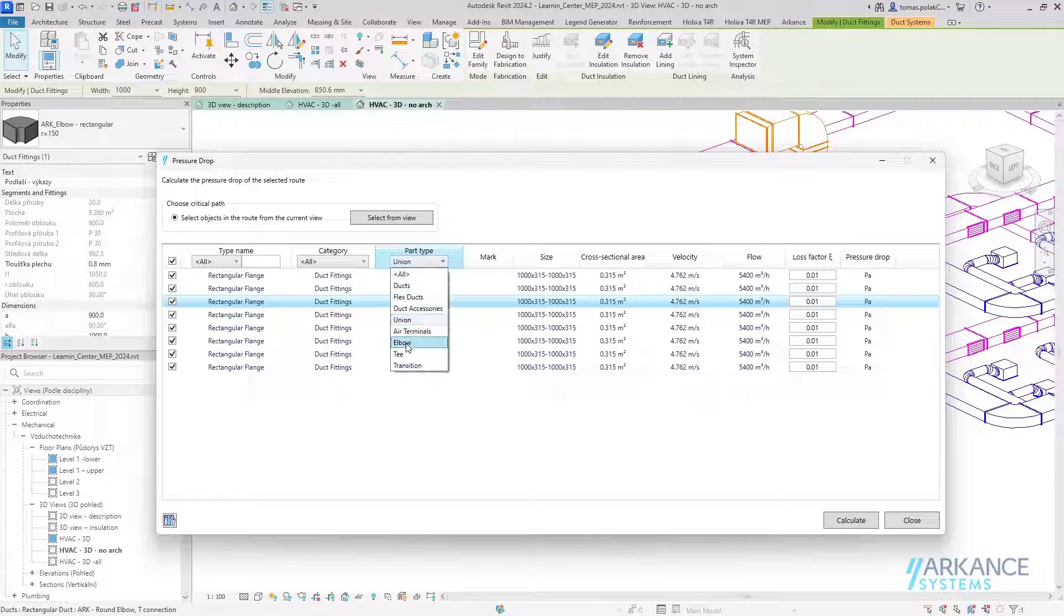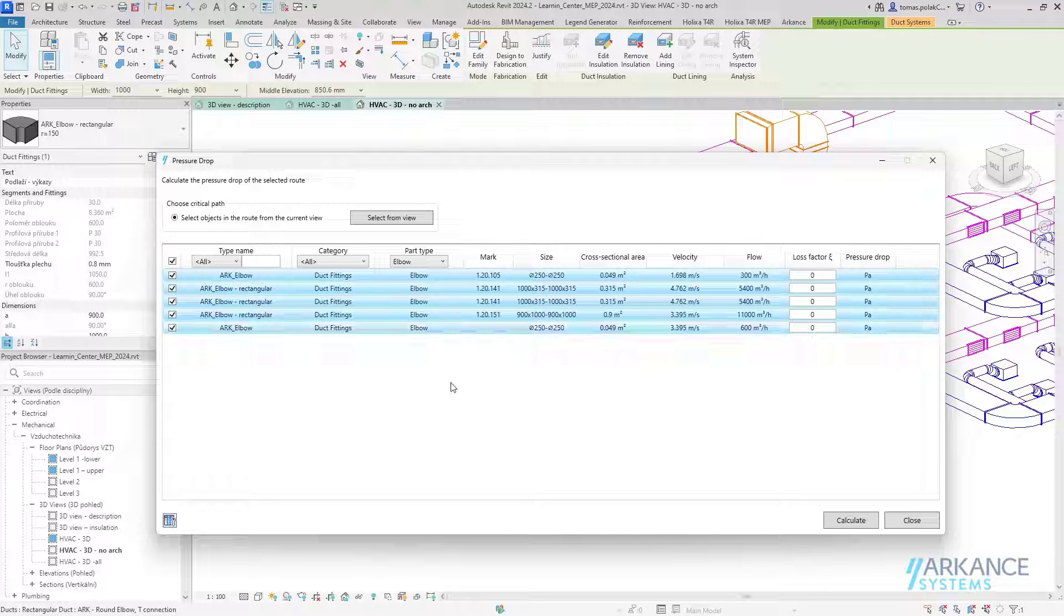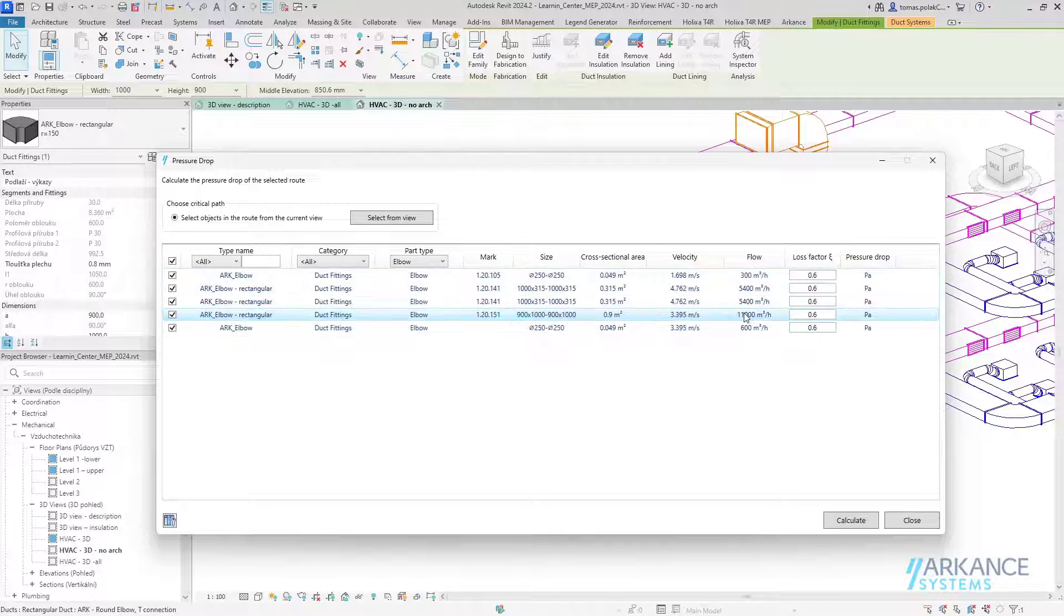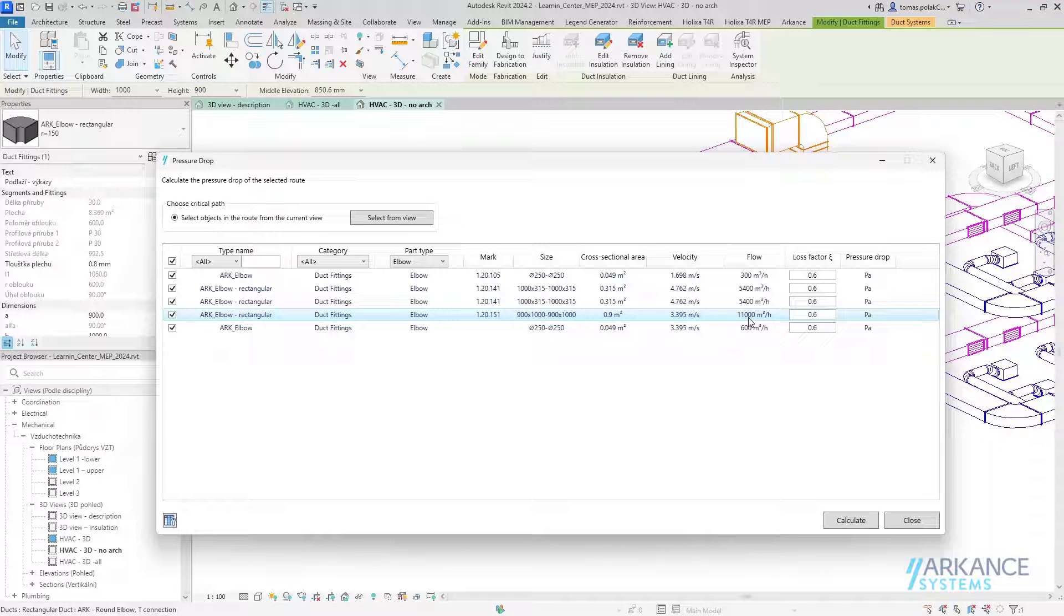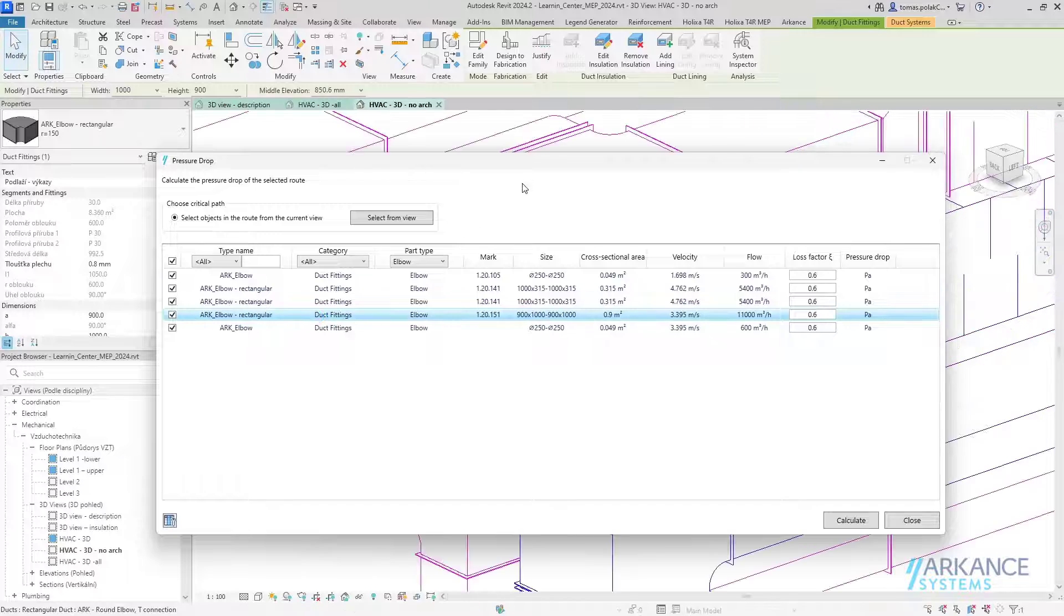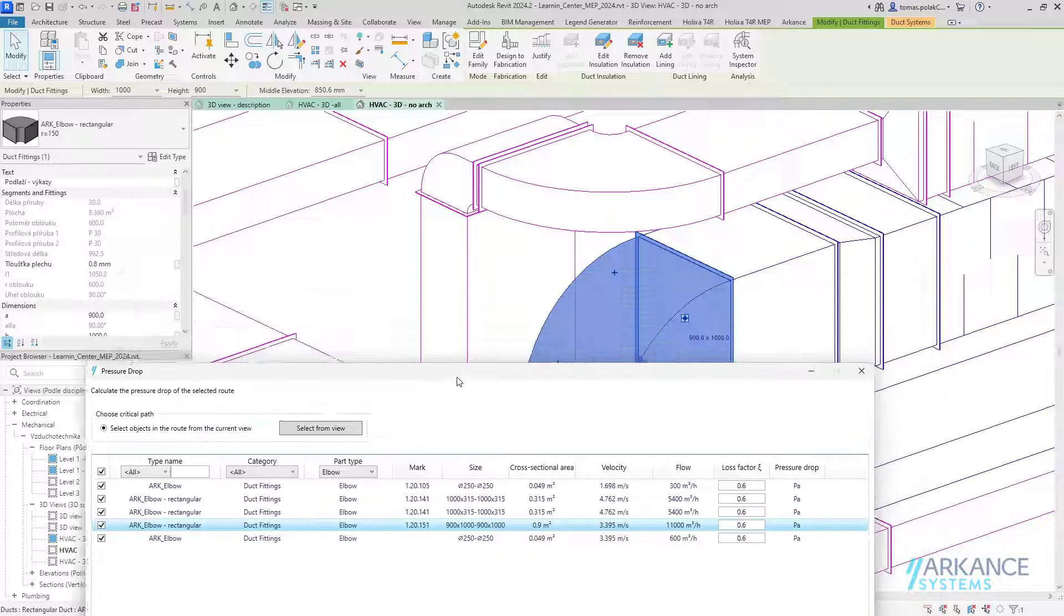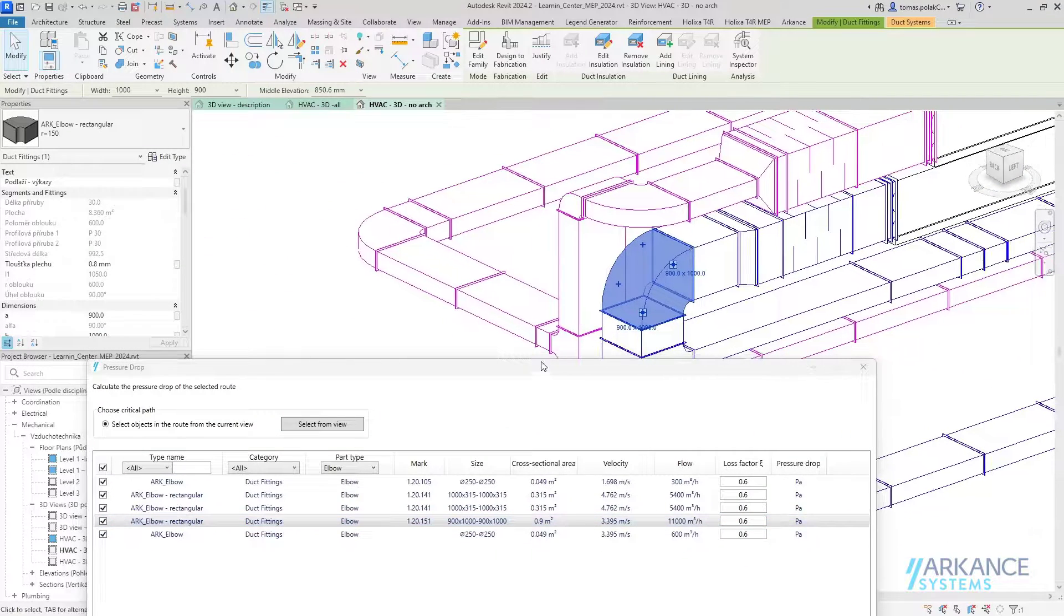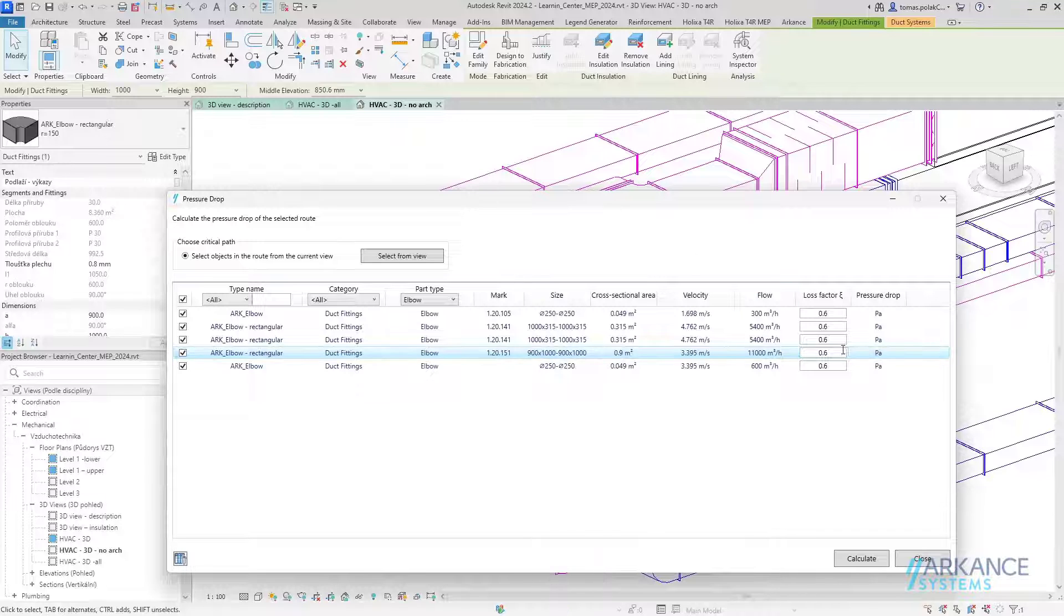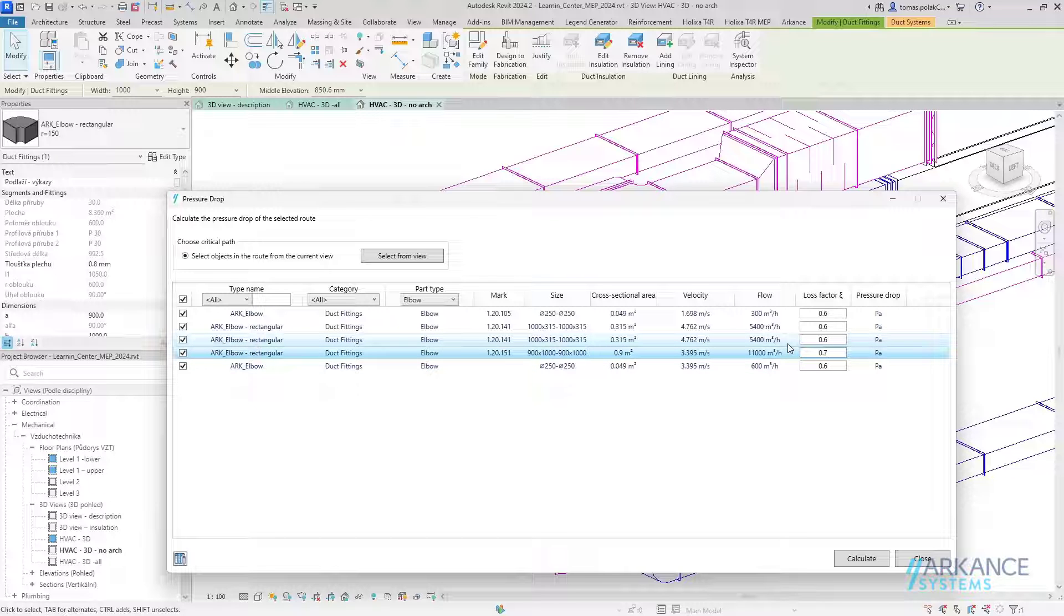Now let's filter out elbows. Let's shift-select all of the elbows and add the loss factor 0.6 to all of them. For this one which has a higher flow, I will double-click it so I know which one it is. Let's say it has a different loss factor of 0.7, so I will input 0.7.